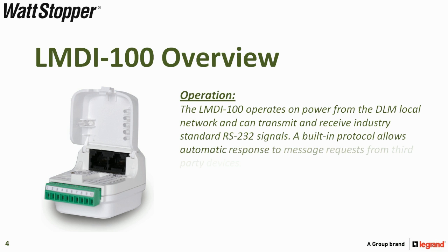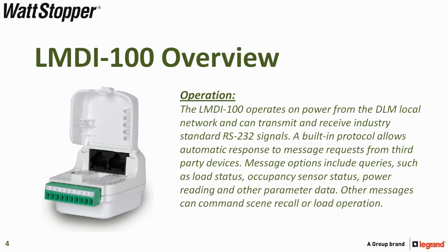The LMDI100 operates on power from the DLM local network and can transmit and receive industry standard RS-232 signals. A built-in protocol allows automatic response to message requests from third-party devices. Message options include queries such as load status, occupancy sensor status, power reading, and other parameter data. Other messages can command scene recall or load operation.